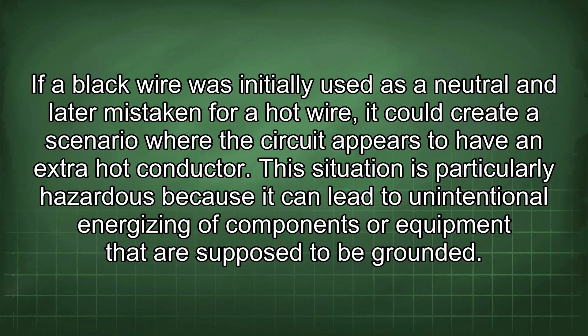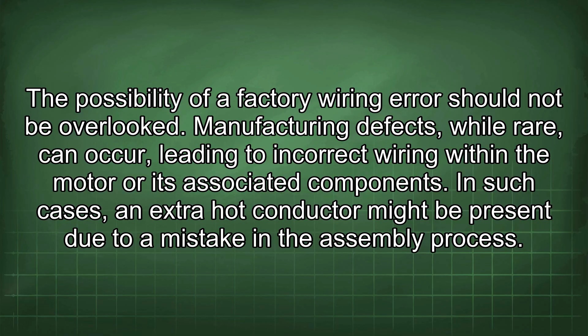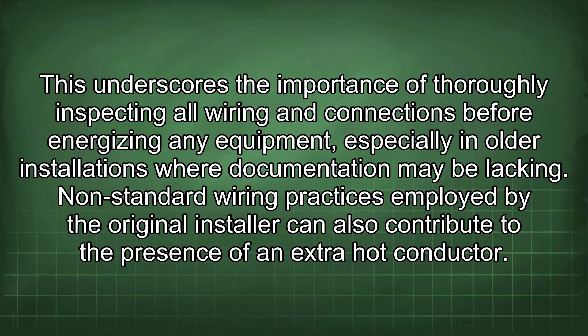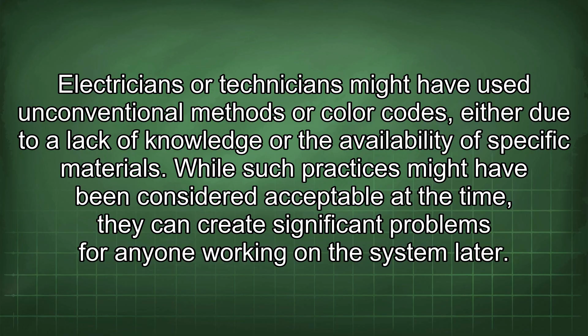Manufacturing defects, while rare, can occur, leading to incorrect wiring within the motor or its associated components. In such cases, an extra hot conductor might be present due to a mistake in the assembly process. This underscores the importance of thoroughly inspecting all wiring and connections before energizing any equipment, especially in older installations where documentation may be lacking. Non-standard wiring practices employed by the original installer can also contribute to the presence of an extra hot conductor. Electricians or technicians might have used unconventional methods or color codes, either due to a lack of knowledge or the availability of specific materials.